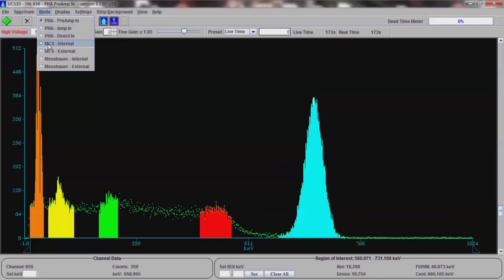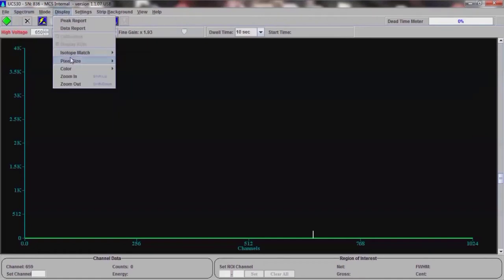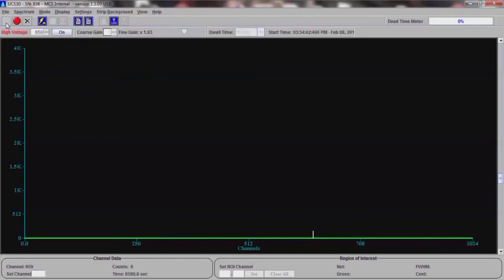So let's switch this now to multi-channel internal scaling. This will allow us to count time and counts. We'll set each channel to be about two seconds worth of time, so the channels will move across dwelling for two seconds at a time and count up, as you can see here, for the number of counts that fill each one of those two second channels. We'll change the pixel size to be a little bigger - maybe that'll be easier for you folks to see - and let's start calculating.